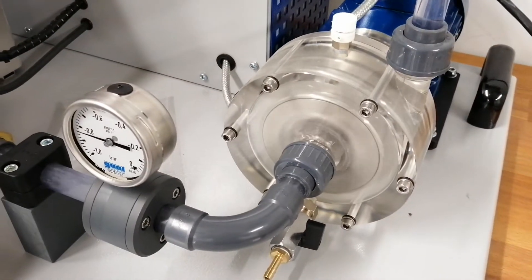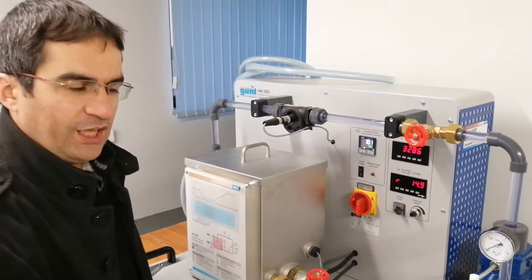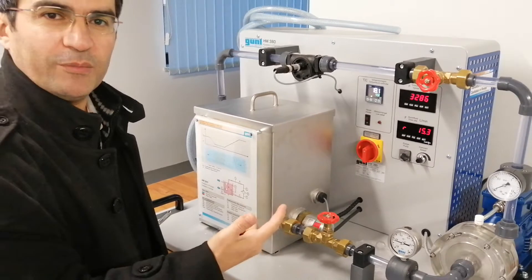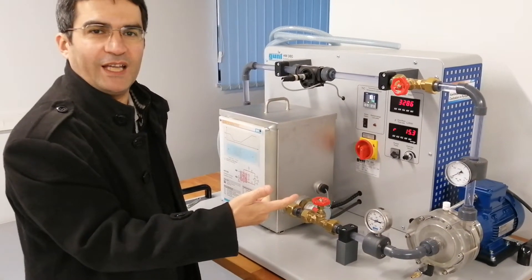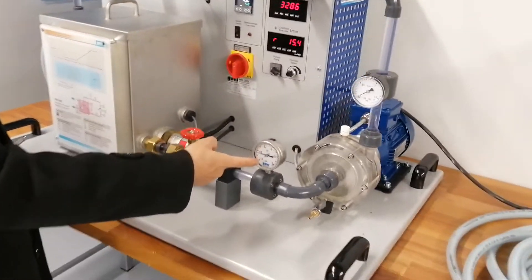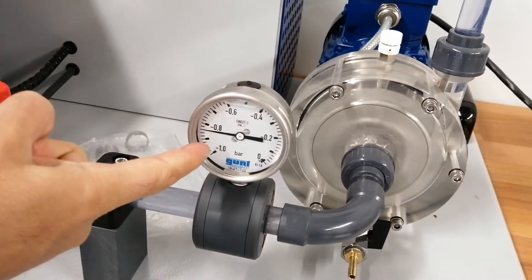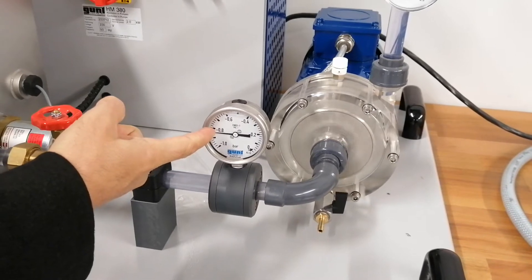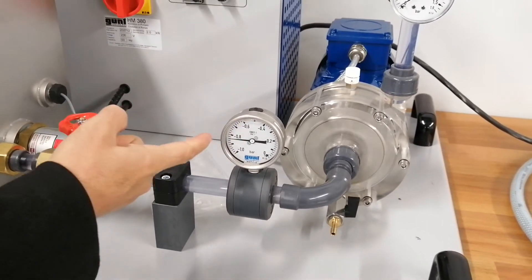Those bubbles are very dangerous for structure. Especially in turbines and also pumps, metallic materials. It can make corrosion over time. And then also you can see the input pressure. There is a suction, as you see. Zero, nearly minus 0.8, as you see.